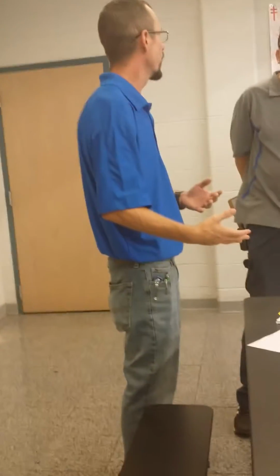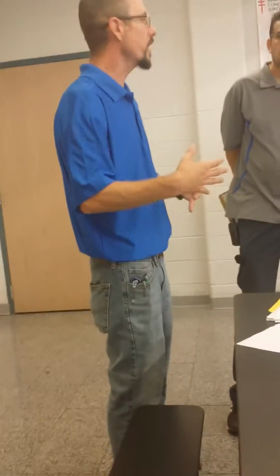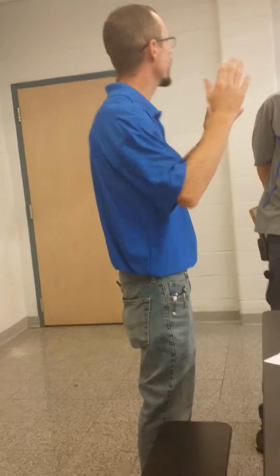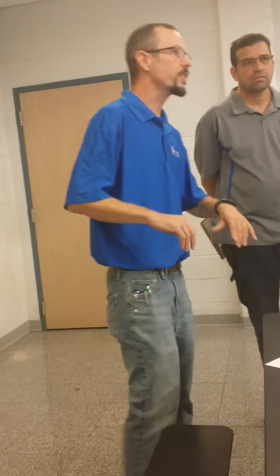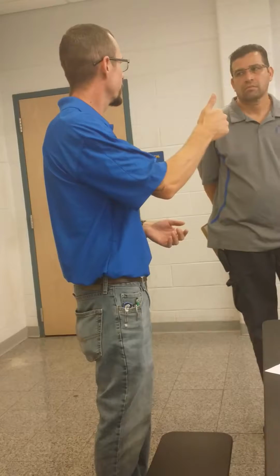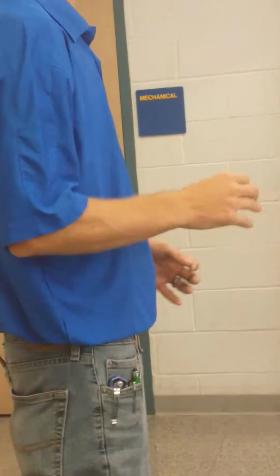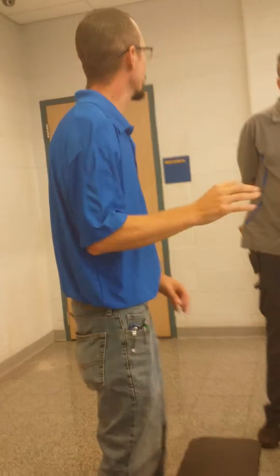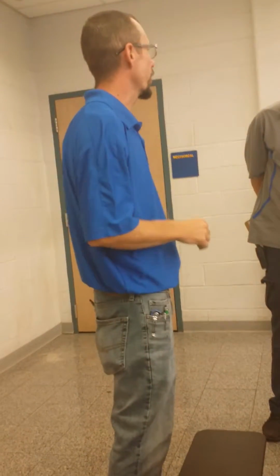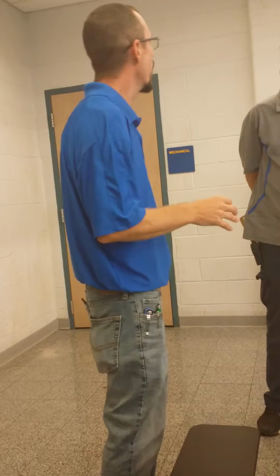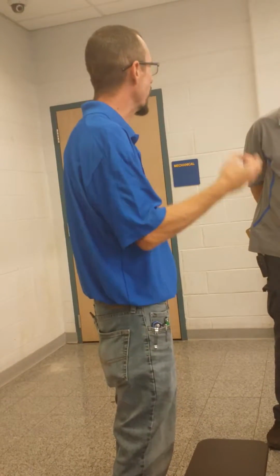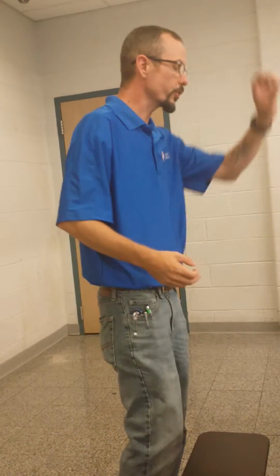You may find that certain classrooms, like your wood shop and stuff like that, may need it a bit more often. During that maintenance, you should be giving a visual inspection of the system itself. You should be taking a look inside the control panel and taking a look at the wiring, your line voltage wiring and control wiring. Just a visual inspection. You want to make sure that we don't see anything out of the norm, and that's why the visual inspection is important. We take a screwdriver, we open up the panel, and actually look at the inside of it.